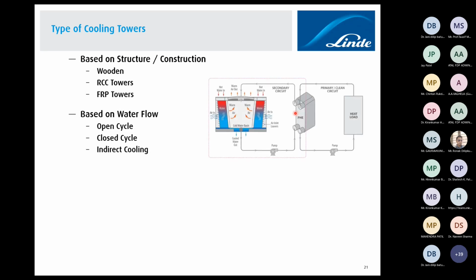Indirect cooling is nothing but the cooling tower giving the water to only one intended heat exchanger. Here is a plate heat exchanger. That plate heat exchanger is exchanging the heat in the secondary circuit. This is why it is called indirect cooling. So this cooling tower is just installed to take care of a series of plate heat exchangers. And why is this kind of arrangement done? Because, let's say, if you are not doing this and you are connecting both the circuits together with the same pump, then what will happen? This cooling water would be faced by all the heat exchangers connected in the industries.